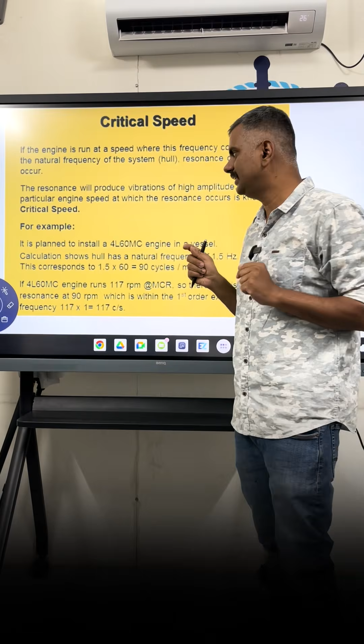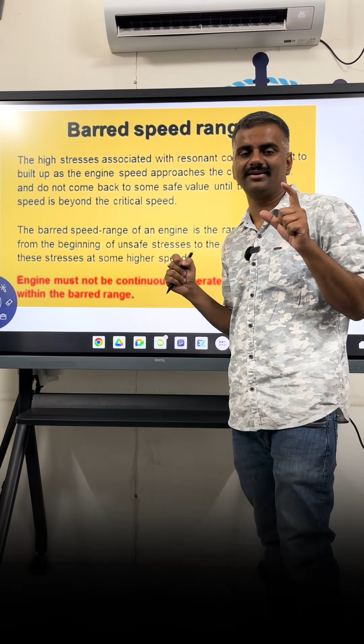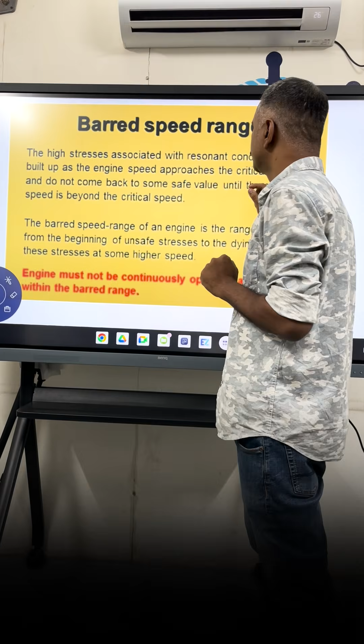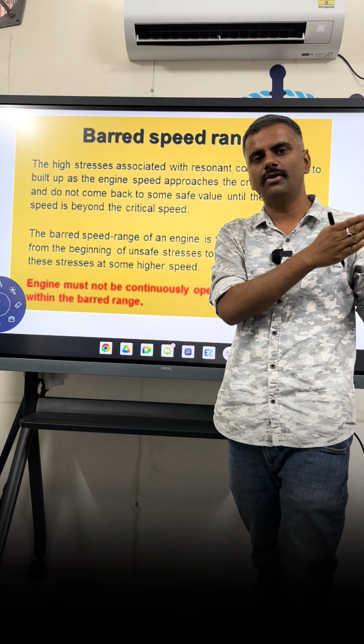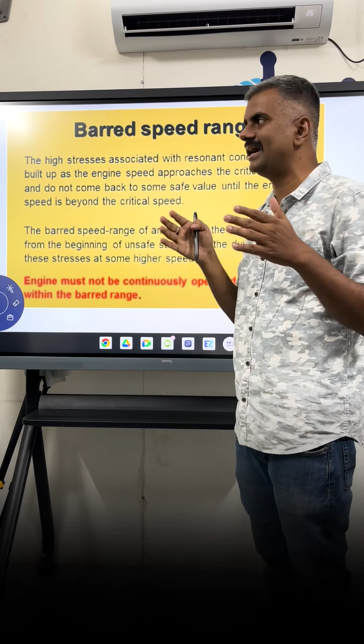When the engine is manufactured, the critical speeds are determined by the engine manufacturers. What is the relation between the barred speed range and the critical speed is very commonly asked in your MEO class examinations. The barred speed range is the range where this scenario of matching of frequency can start. The amplitudes rise, not suddenly, but they come closer to each other at a certain level of condition, at certain RPM.